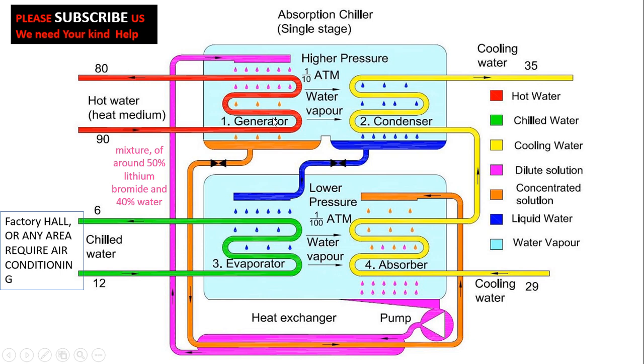Due to boiling point differences and different chemical properties, the water in the lithium bromide solution vaporizes at this temperature and pressure, while the lithium bromide itself does not evaporate — it remains in liquid form. So in the generator, the lithium bromide solution is separated: water vapors move toward the condenser, and the lithium bromide solution stays in liquid form.